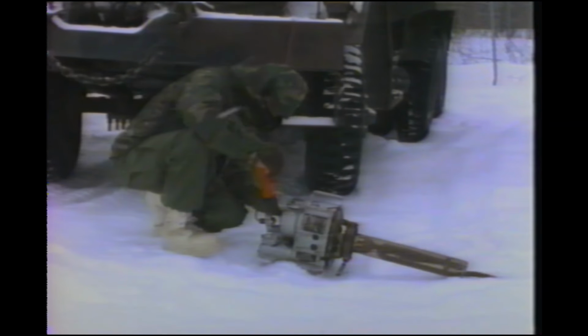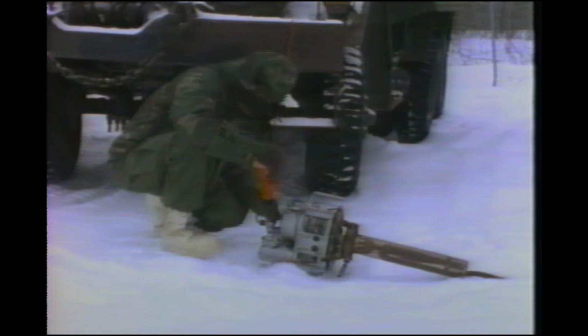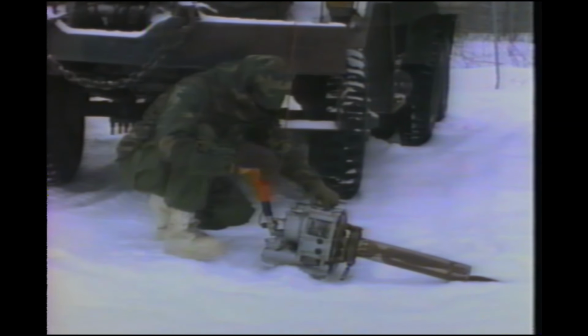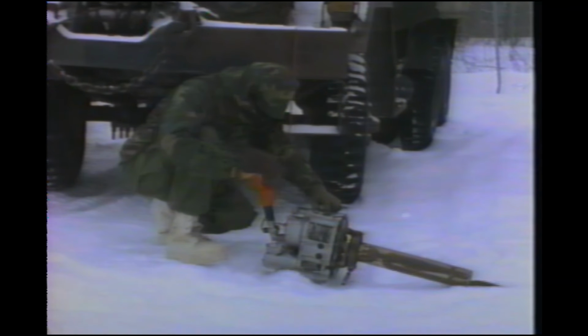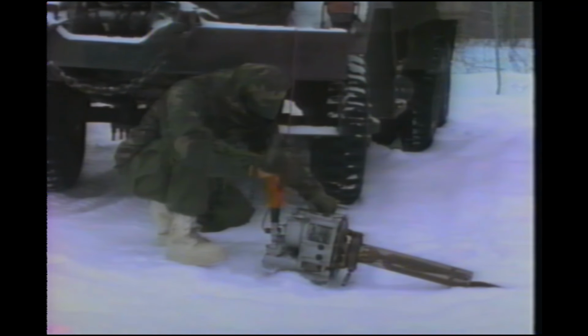Move the hand pump lever back and forth several times in a slow, firm, and regular manner. Pumping the lever too fast will flood the heater. If it's available, a handle from an unserviceable shovel will keep the ignition switch depressed and also make it easier to pump the Swingfire. In temperatures below zero, it will be necessary to depress the ignition switch on the lever for some time to activate the preheating plug before pumping fuel into the Swingfire.